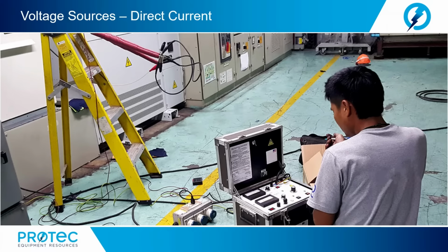Well, let's start with direct current. For years, high voltage DC testing has been the traditionally accepted method for judging the serviceability of high capacitive devices such as medium voltage cables. Direct current tests have worked well for conducting high potential and condition assessment tests on paper insulated lead covered, or PILC, cable. Now, when plastic insulated cables were first introduced in the 1960s, DC continued to be the preferred method.